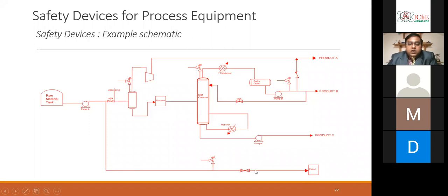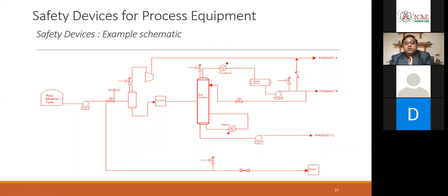For this line, it is designed for pump shutoff. It is designed for a 600 pound rating, but there is a valve here. So if I close this valve, there will be liquid entrapped here, which will be a thermal expansion scenario. So I have put a thermal relief valve here. So if I go now here, you see in the column there is a PSV. So what can be the probable cases? Can anyone tell me for the sizing of this relief valve?